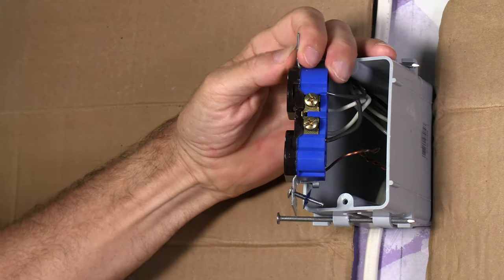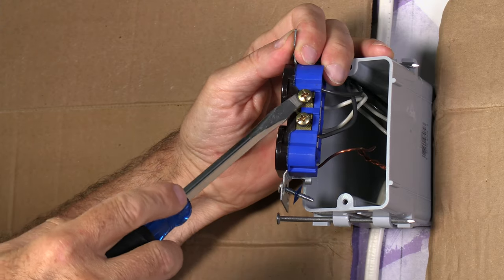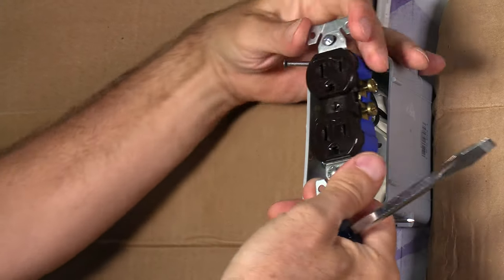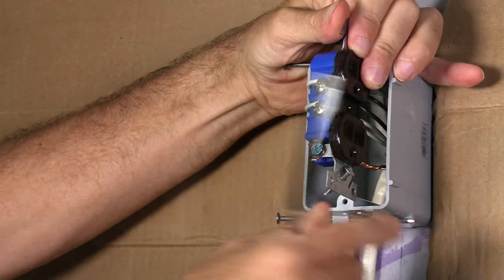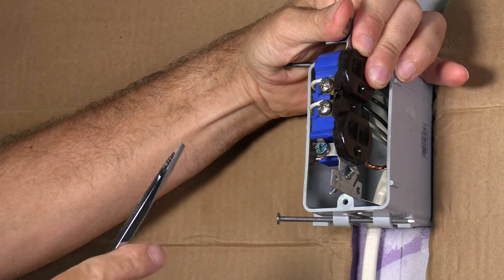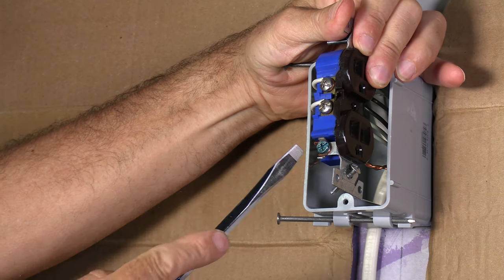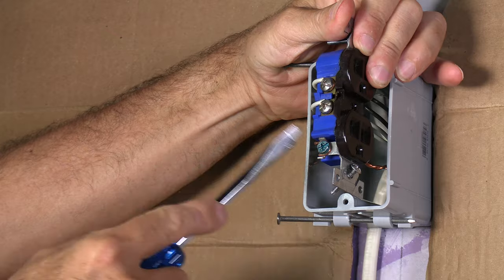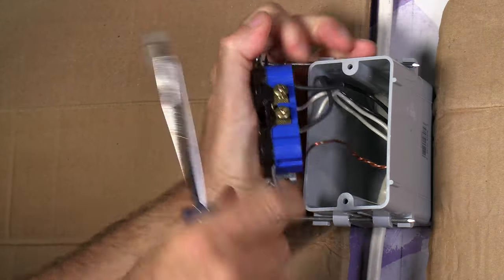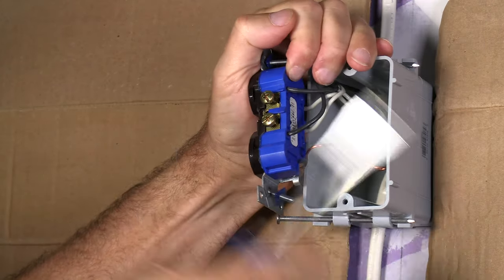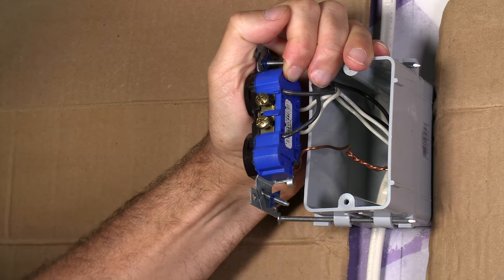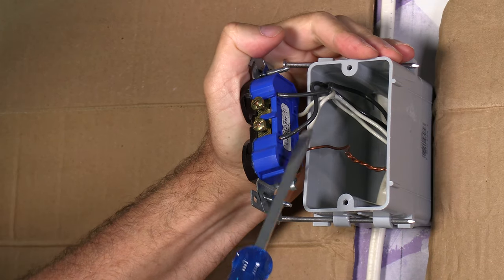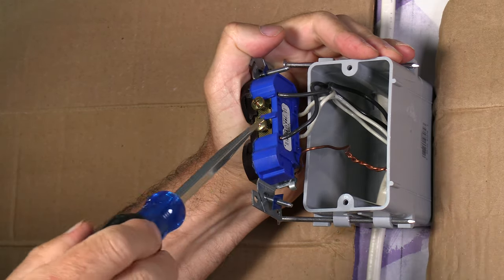So on the right side here, we have these brass screws that go to the hot side. And on the left hand side, we have the silver screws on the neutral side. And also we have a green screw on the ground. We use the black wire for hot over here on the brass screw side. So you have your black wires coming here and the white wire is going over there.